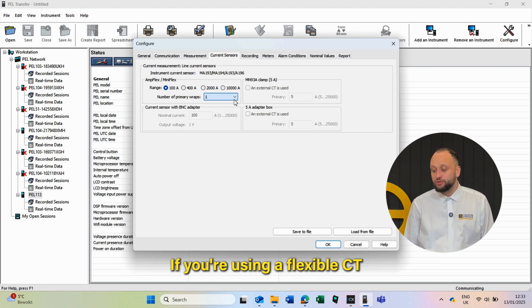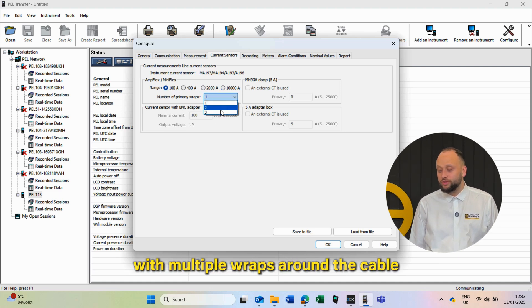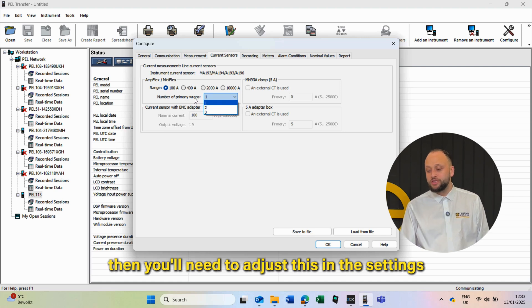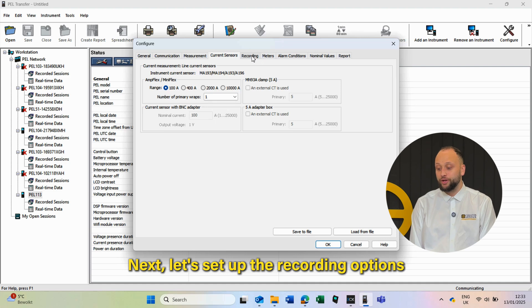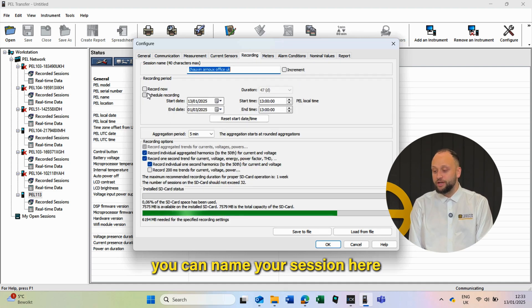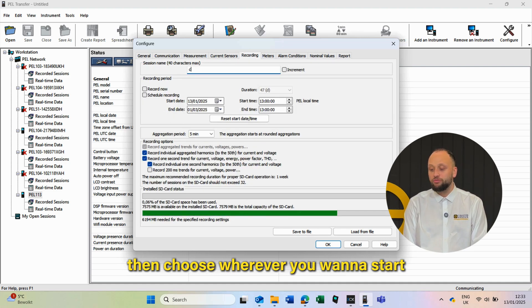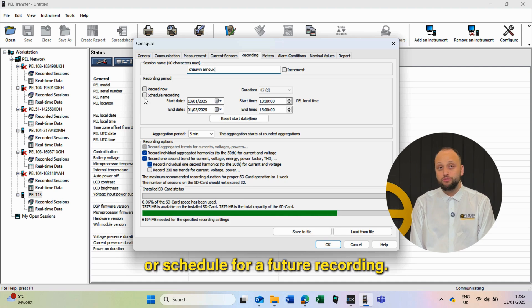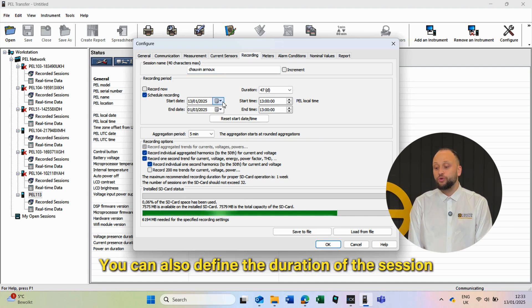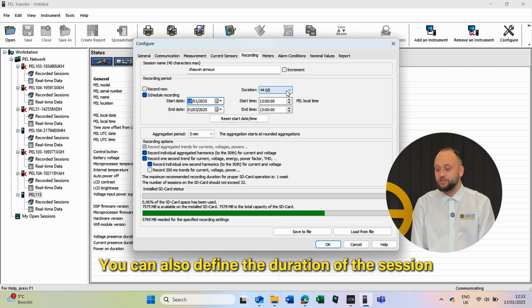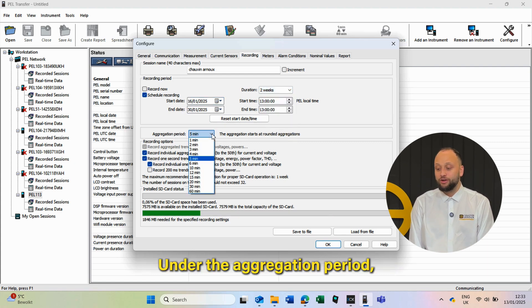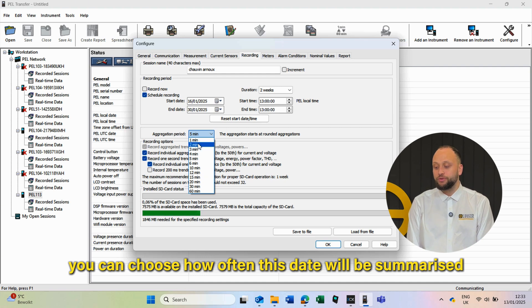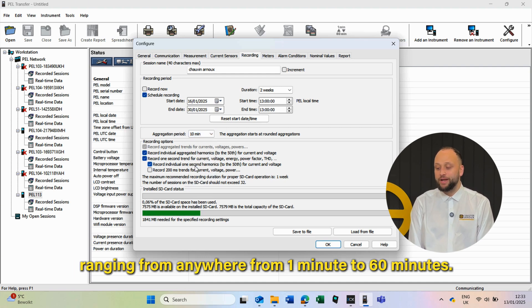If you're using a flexible CT with multiple wraps around the cable, then you'll need to adjust this in the settings to reflect the number of wraps. Next, let's set up the recording options. You can name your session here, then choose whether you want to start recording immediately or schedule a future recording. You can also define the duration of the session or set the exact start and stop times. Under the Aggregation Period, you can choose how often the data will be summarized, ranging from 1 minute to 60 minutes.